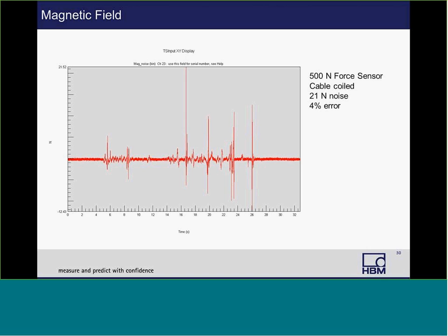Now, what I did was probably not very common, especially at test labs, but you need to be aware that magnets or magnetic fields can really cause a signal distortion. Because once again, I said this load cell had a properly shielded cable, or the proper Faraday cage.